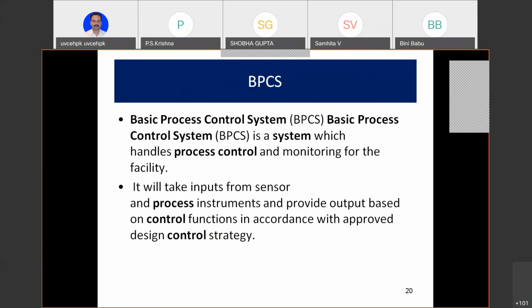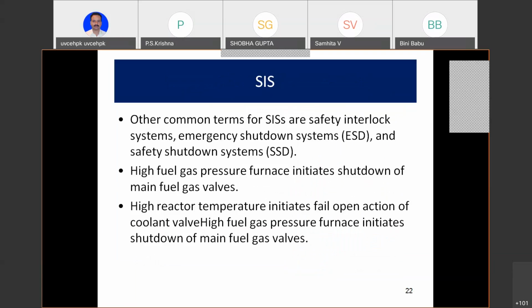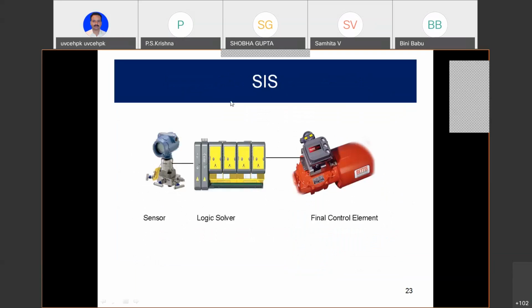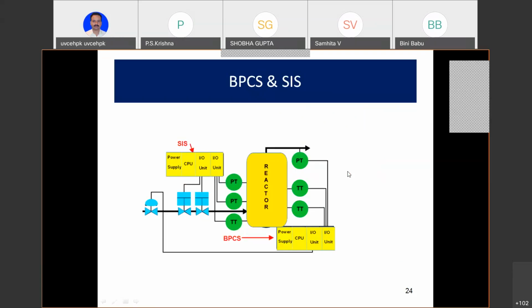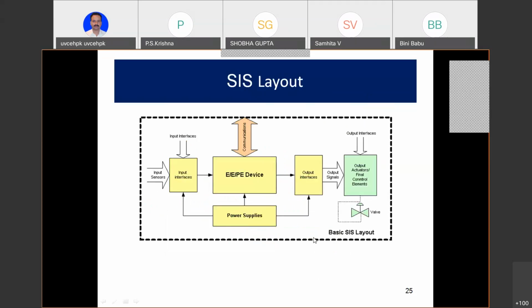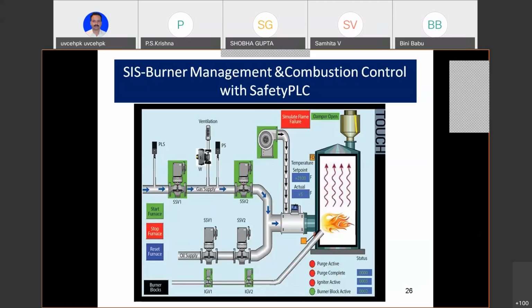Now, I will not take any time on the BPCS or the SIS. I will take you straight into this. This is like a kid's diagram to show that this is your sensor, this is your logic solver, and this is your final control element. Okay, this is not a big deal. This is showing you both together, and you're already familiar because in that diagram, however imperfectly drawn, in the first part of the presentation, you saw that there is a green PT and a red diamond. Here, the safety instrumented system has a separate PLC, and this BPCS has a separate one. This is how the other things, interfaces, power supplies are shown. Nothing different, it is independent.